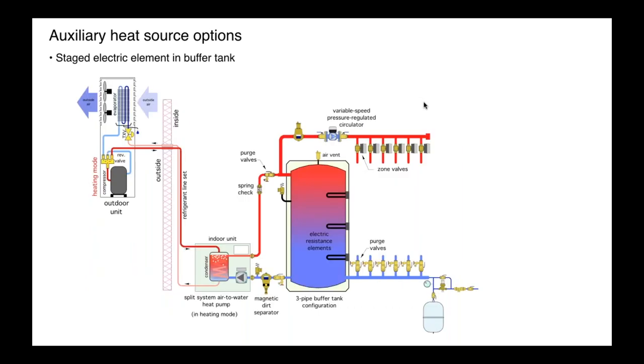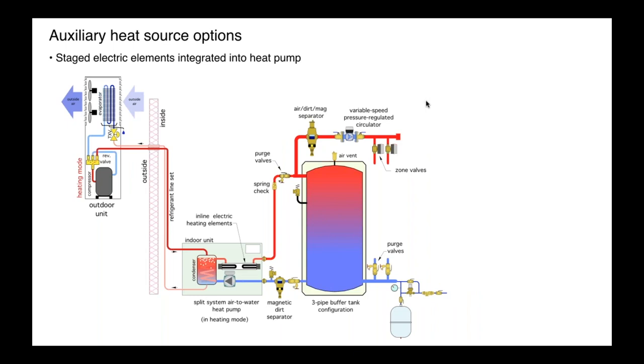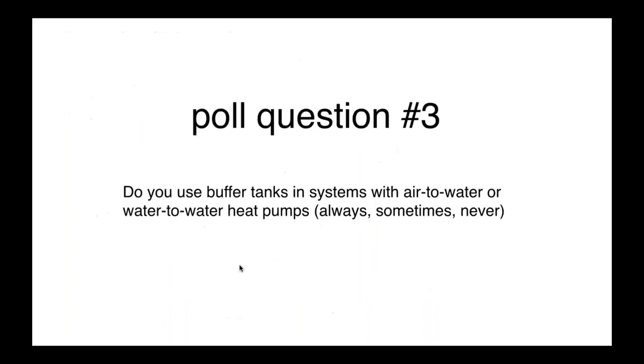You can get buffer tanks with built-in electric elements from different manufacturers. This is essentially just putting the elements in the tank instead of hooking up an electric boiler. Okay. And another option, at least one manufacturer of air-to-water systems today actually builds in, I believe, two 6 kW elements. So that's a 12 kW auxiliary that's built right into the heat pump, and the controls to operate those are integrated right into the heat pump. So essentially there's no requirement for elements in the tank or a separate auxiliary boiler. Okay. Again, all these drawings, I'm going kind of fast. All these drawings are in idronics 27.